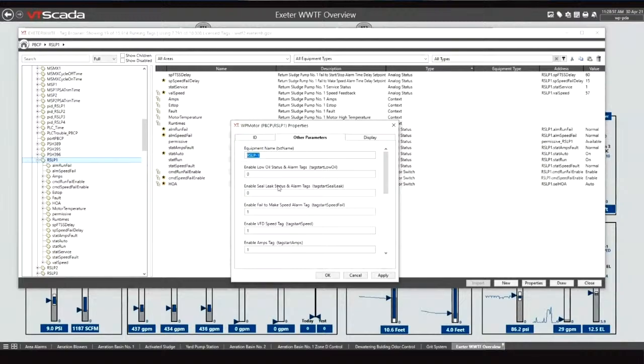We can give it a name, and enable and disable different children based on whether this piece of equipment has, say, a seal leak. This piece of equipment does not have a seal leak alarm, so we put a 0 in this parameter, and that disables all I/O associated with it. It's great for not using up your I/O tag count, because as soon as we disable this, it removes that from the tags you pay for.